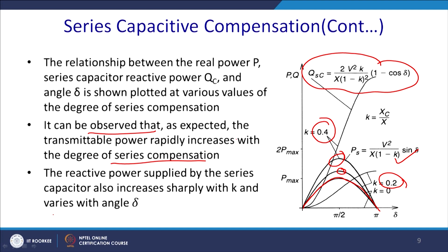Now, converter type series compensation. This kind of compensation is analogous to the SVC in the case of shunt compensation. What you generally do is minimize the value of the impedance, and thus you get enhanced power handling capability, real as well as reactive, of the line, at the cost of reduced impedance. So, current will be high and thermal losses will be high. These are a few issues. Let us see another type of series compensation.